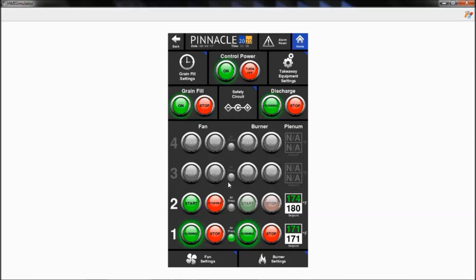We had a minimum speed on the VFD set at 5 hertz out of 60. So if you entered 0% discharge, it was still running at 5 hertz. What we've done is rescale that and put a minimum of 10%, so that it's more genuine to the user exactly how to change speeds at those low ranges. If you were to change from, say, 1% to 2%, you might think you've doubled the speed, but you've really gone from 5 hertz to 5.5 hertz or something similar. Now, if you go from 10% to 20%, you have actually doubled your discharge speed.